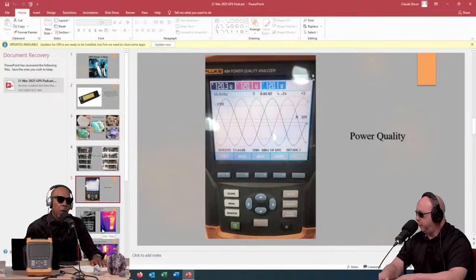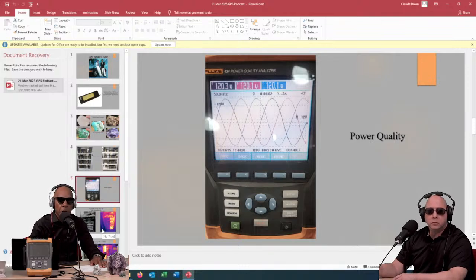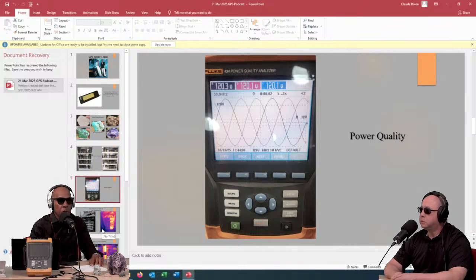I wanted to make sure the audience is clear that this analysis is done simultaneously with the load testing and load banking, since that takes 4 to 5 hours on average. So we're running this meter for 4 to 5 hours too, monitoring it. There are images that can be printed, and some of them end up in the test report at the end, which is substantial.